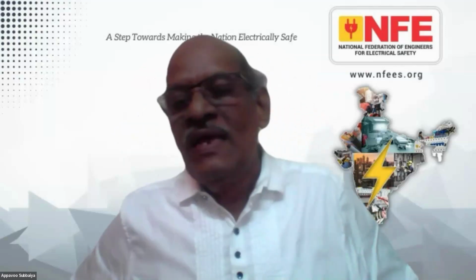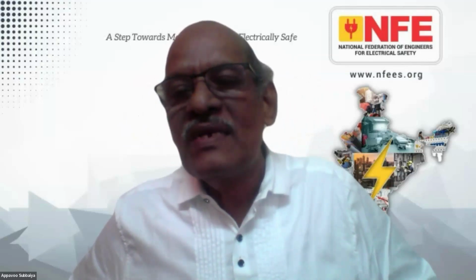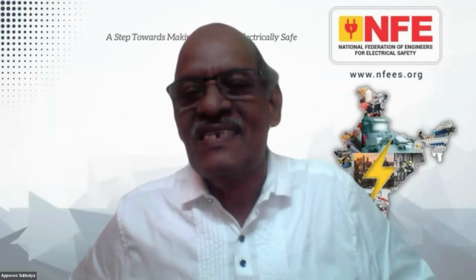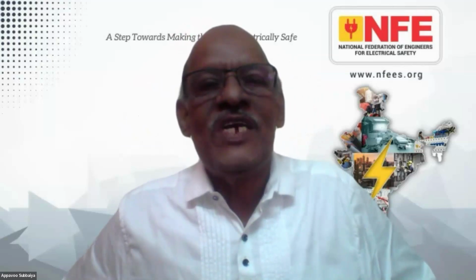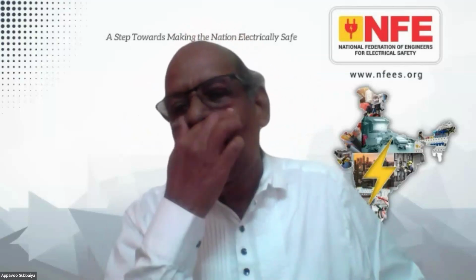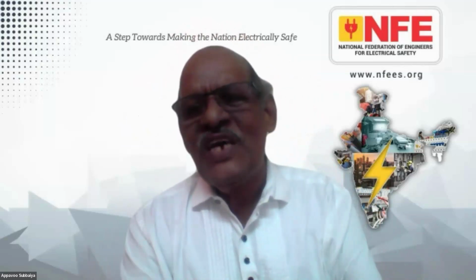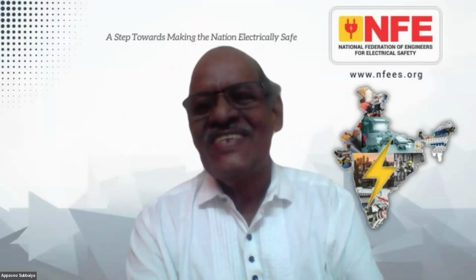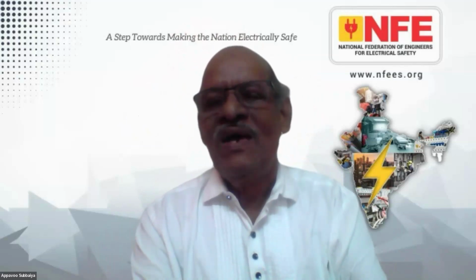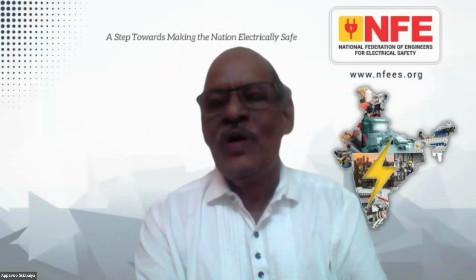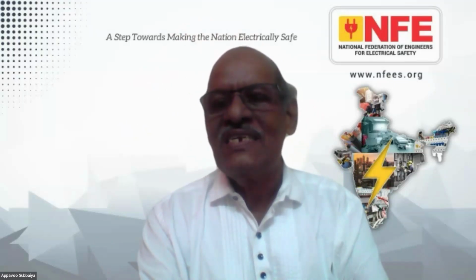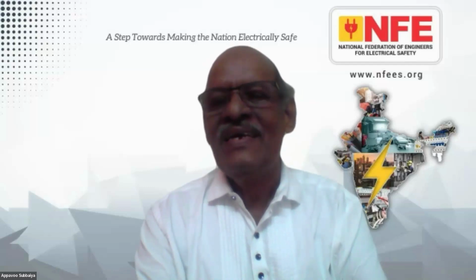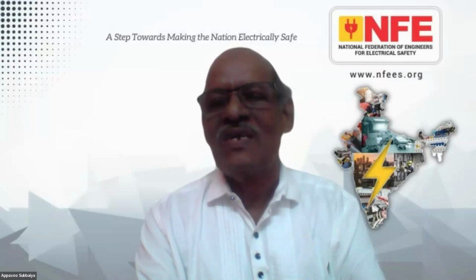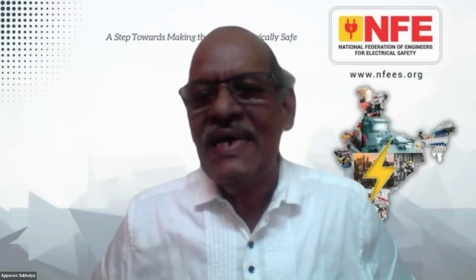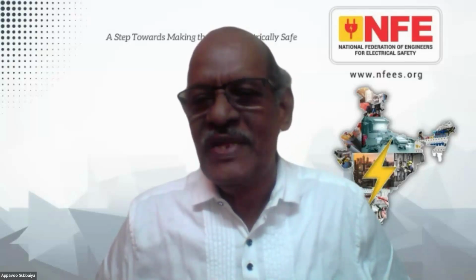Sir, your question is a very big issue, but let us restrict it to the consumer installation, as already explained earlier. See, for the benefit of the doubt, you provide an RCD. Strictly speaking, if you measure the earth loop impedance and find your OCPD can act, you are at liberty. But as per regulation, whether or not your earth loop impedance is within the norms, you have to provide an RCD at the point of supply.